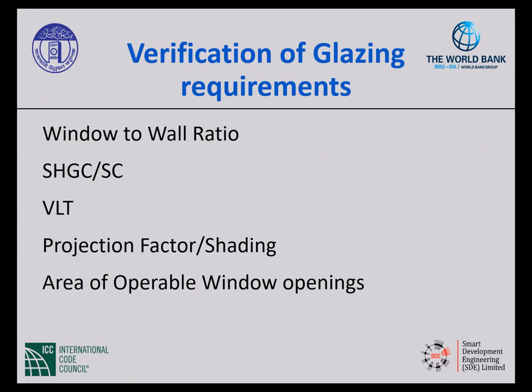All right, so we've talked about all of the glazing requirements found here in Chapter 4, and so let's talk about now how to verify those requirements. Who looks at all of that, and how do we do that? Most of the time, a lot of the verification on windows comes in at plan review. This is the plan reviewers looking at the window to wall ratio to make sure that it's calculated correctly. So the designer has to make sure that they include those window to wall ratios on the plans.